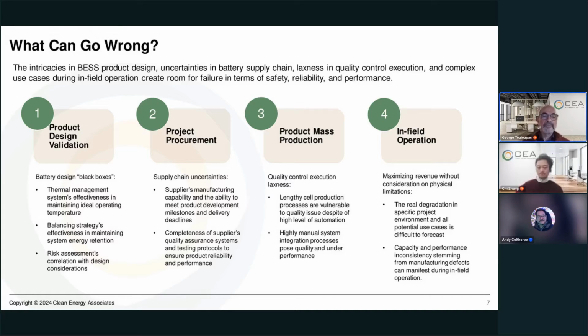Starting at the product design validation, we observe that product design can be reviewed and examined by a third party, but more or less it's a black box. It does contain some very critical subsystems, for example the thermal management system. Its effectiveness is really important for the lifetime of the battery energy storage system, its performance, and of course for safety.